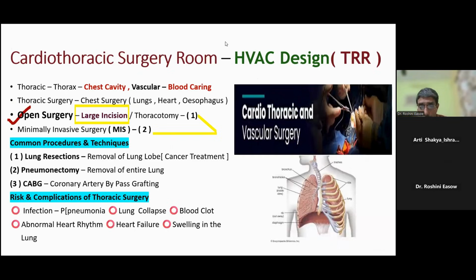How to find the positive pressure maintained in OT or BMT as per design? That is what he actually wants to know. Now, I'm giving an answer. You find a few consultants and contractors use a negative pressure. Even in some journals I find that some are using negative pressure. There is no negative pressure. This negative pressure concept came after COVID.